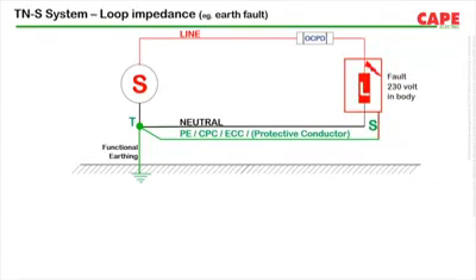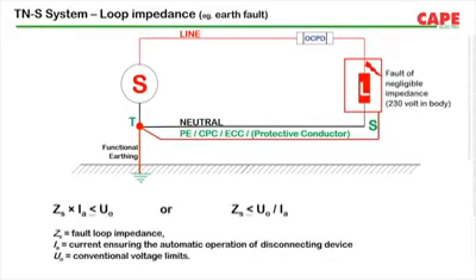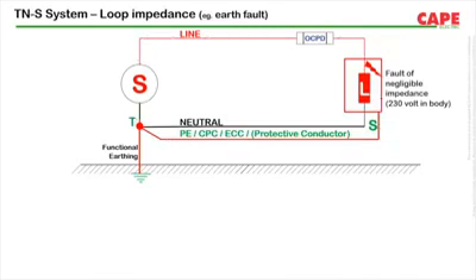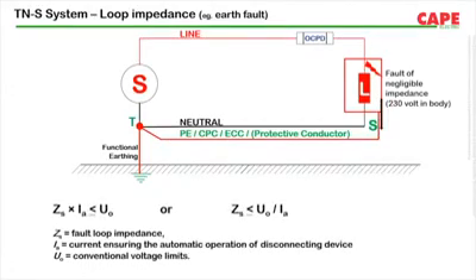Due to an earth fault of negligible impedance in the equipment, the exposed metallic part in the equipment becomes live. As a result, fault current flows through the protective conductor to the neutral of the source, through the winding of the source and then through the line conductor back to the fault. Impedance of this closed loop, starting from the fault and returning back to the fault, decides the amount of fault current. The amount of fault current as multiples of line current decides the disconnection time. In order to achieve quick disconnection, fault loop impedance shall be kept minimum. The IS standard provides a simple formula to calculate the fault loop impedance.